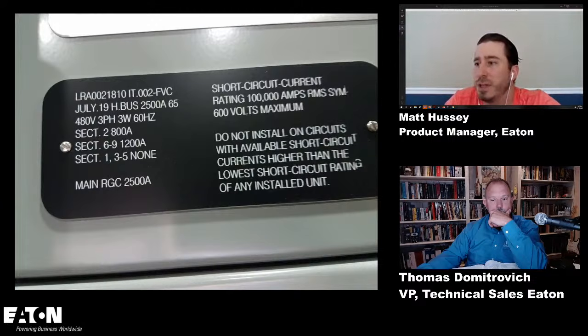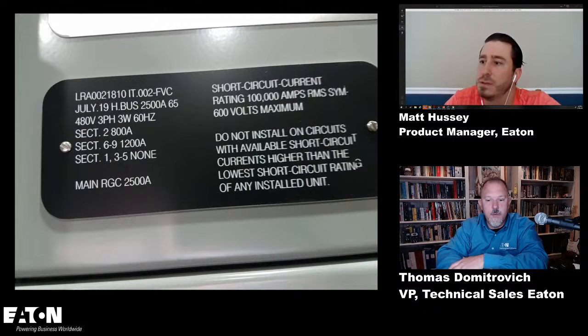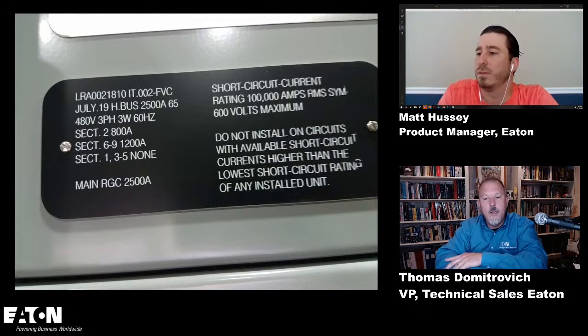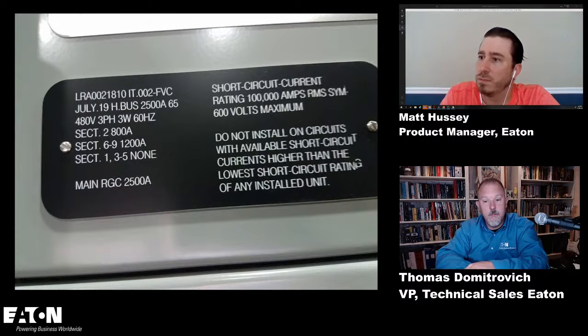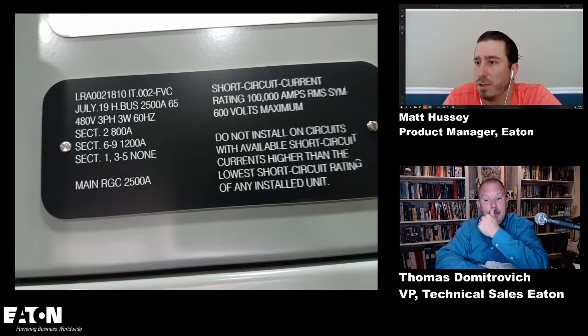In this particular case, it looks like it was a 100 kA lineup being utilized. It says, do not install on circuits with short circuit currents higher than the lowest. Okay, let me ask you this. So this piece of equipment is rated 100,000 amps. Yep. That means that no overcurrent protective device in this equipment can be less than 100,000 amp interrupting rating, right? Correct. Or the combination rating is at least 100 kA. Or the combination rating. That's exactly right.